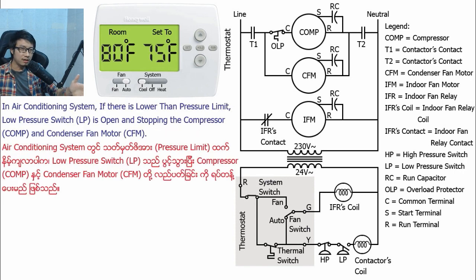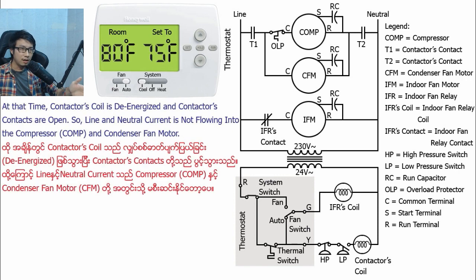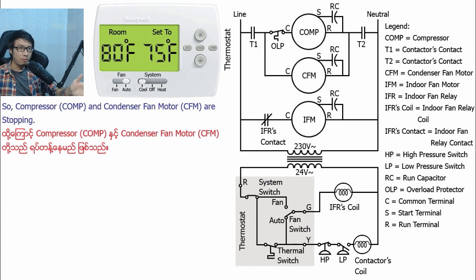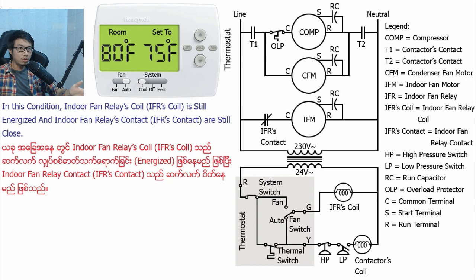In the air conditioning system, if there is a lower suction pressure limit reached, the low-pressure switch opens and stops the compressor and condenser fan motor, because the low-pressure switch disconnects current flowing into the contactor coil. At that time, the contactor coil is de-energized and contactor contacts are open, so line and neutral current is not flowing into the compressor and condenser fan motor and they stop. In this condition, the indoor fan relay coil is still energized and indoor fan relay contacts are still closed, so the indoor fan motor is still running. Thank you very much for watching my video.